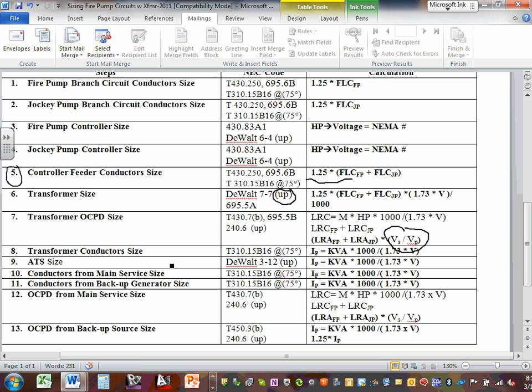Then the transformer conductor. You find the I primary of the transformer and size it basically. Can you guys see that? Auto transfer switch, same thing from the I primary. Conductor from the main service, the same thing, find the I primary. Conductors from the backup generator, same thing. Overcurrent protection device from the service side, exactly the same thing, except look what we do. We have to multiply it by the voltage ratio. Conductor from the backup service, it's basically the 1.25. We size it by 1.25.